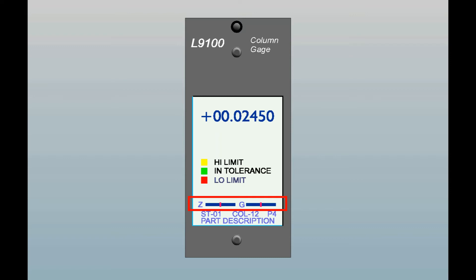The reason for these indicators is that you don't want to be operating the column with either of these two settings at the extreme right or the extreme left of its operating range. To do so means that you are limiting the electronic mastering ability of the column and you may run into error messages when auto mastering. Ideally, the closer these controls are to their mid positions the better off you are, and we will show you how to adjust these positions in another video.